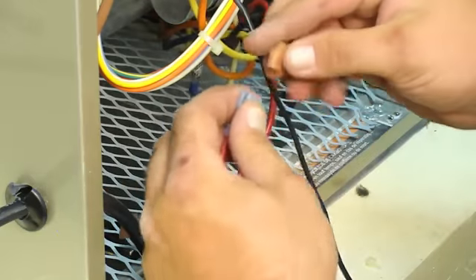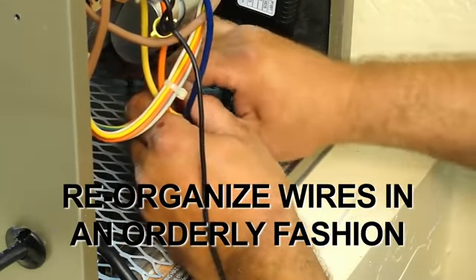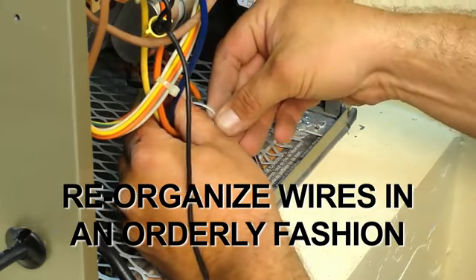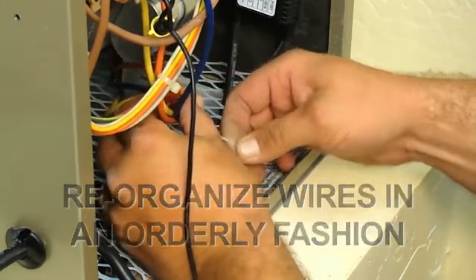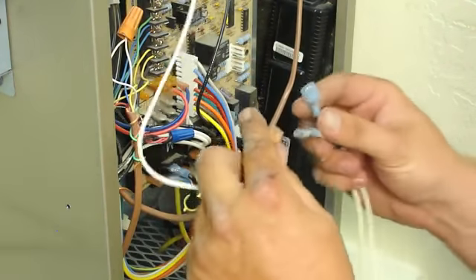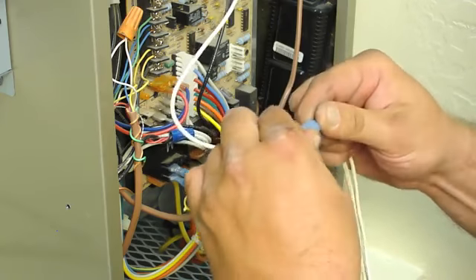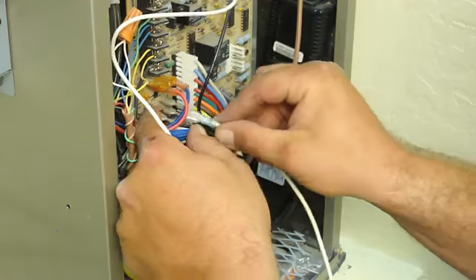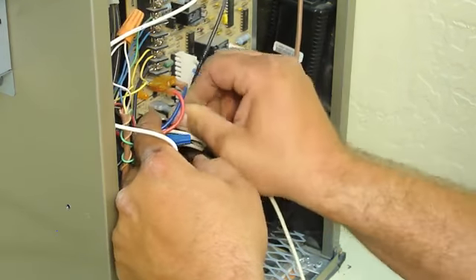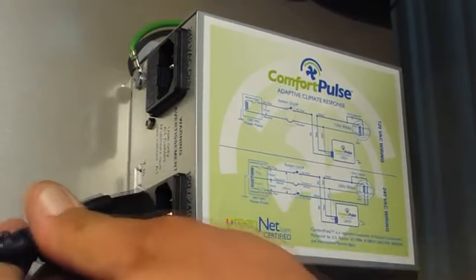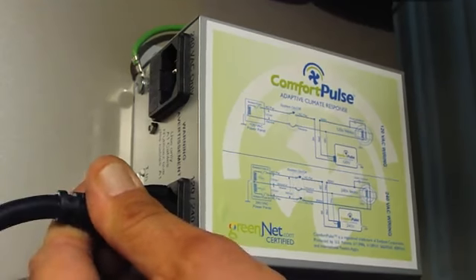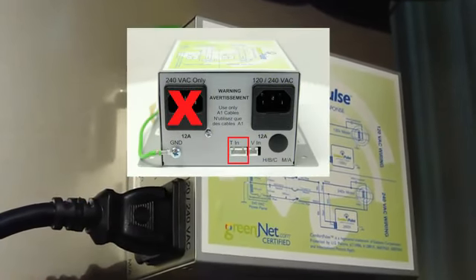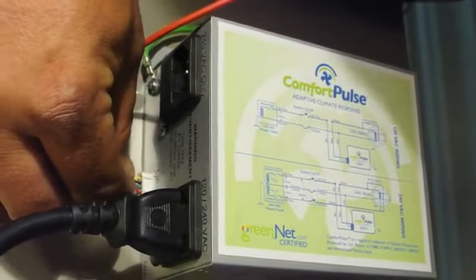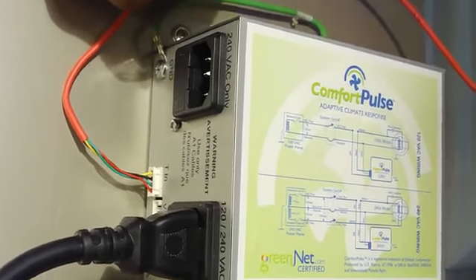Next, connect the Comfort Pulse power cable or red wire to the high speed tap wire that comes from the fan motor. Pull a chassis, ground, or neutral, which is preferred, off the HVAC unit circuit board and connect to one of the white wires on the Comfort Pulse power cable while connecting the other end of the white wire back into the circuit board. Now you can plug the Comfort Pulse power cable into the Comfort Pulse 120 to 240 volt AC plug, never the 240 volt only. Plug the temperature sensor cable into the back of the Comfort Pulse in the connector receptor marked T-in, as indicated on the installation guide.